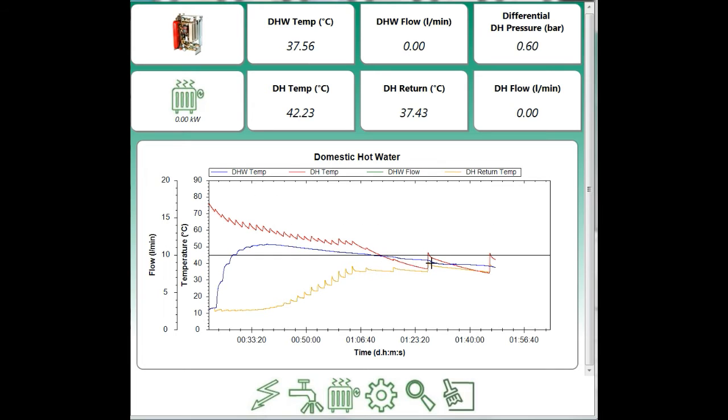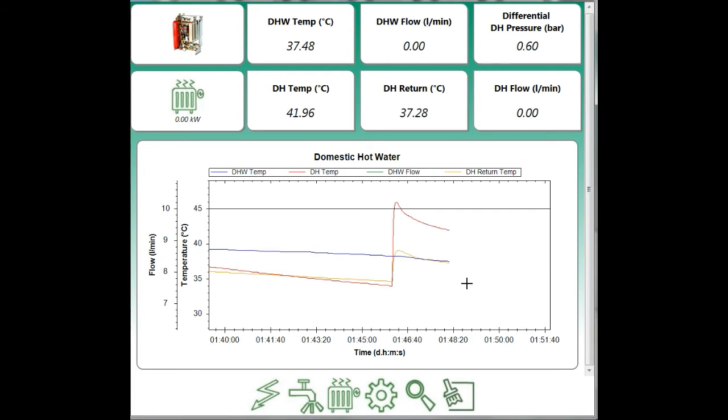Now, if we skip to 15 minutes later, you can see how this has happened. The return temperature, once it's achieved 35 degrees C, the unit stops letting in really any more heat at all. Until the domestic hot water temperature dropped down to the region of 35. At which point the unit starts letting in a small amount again.